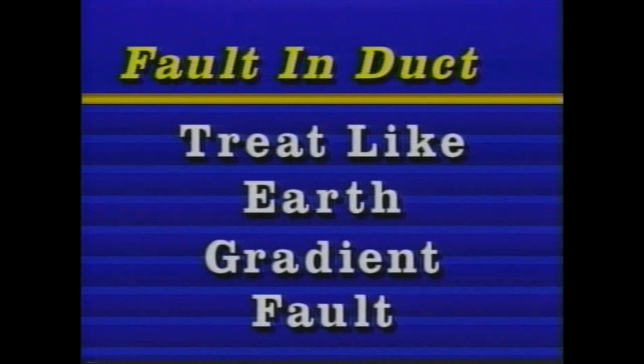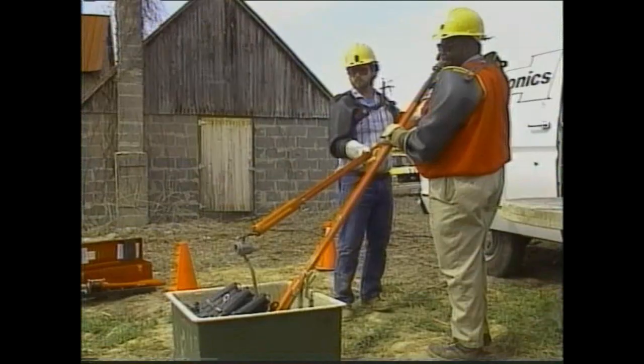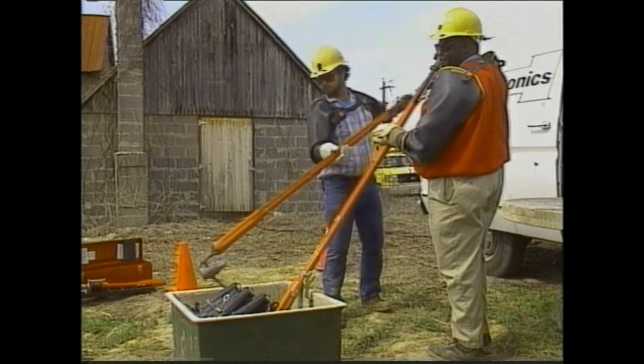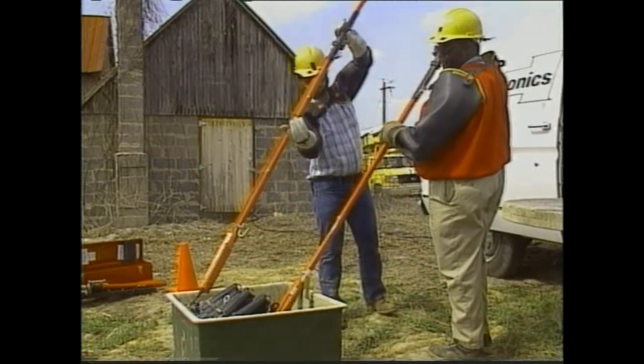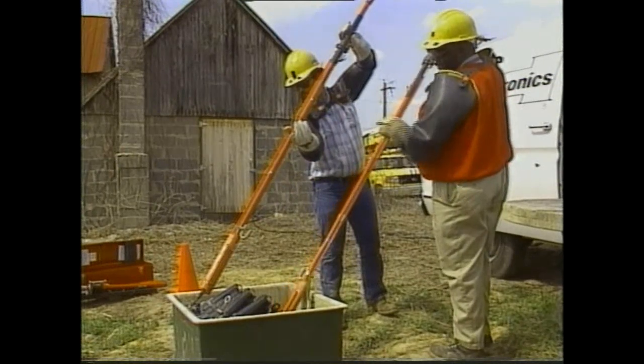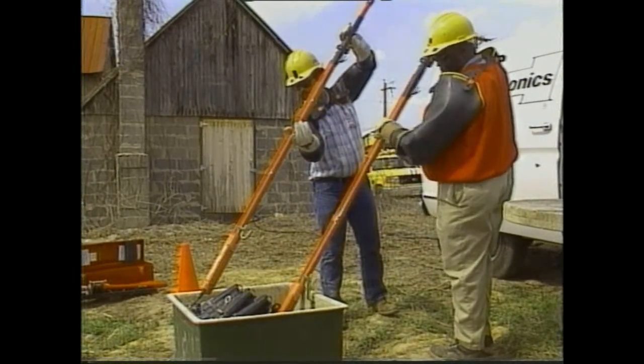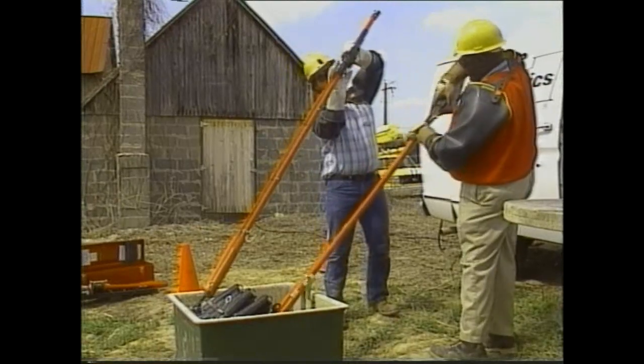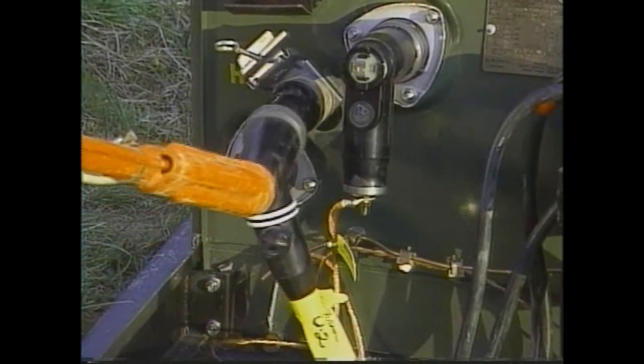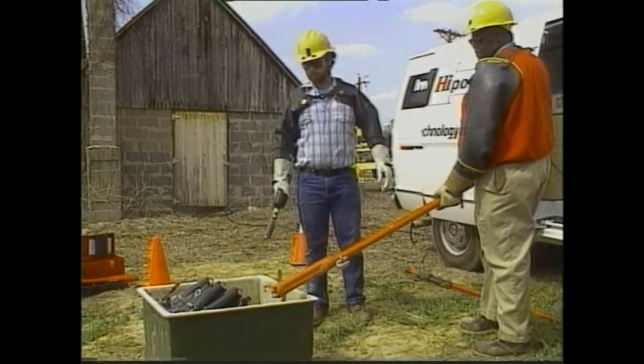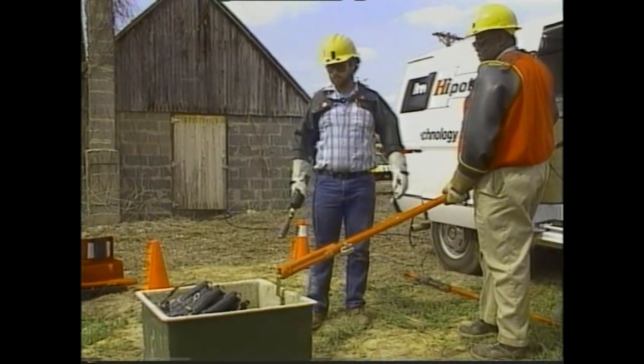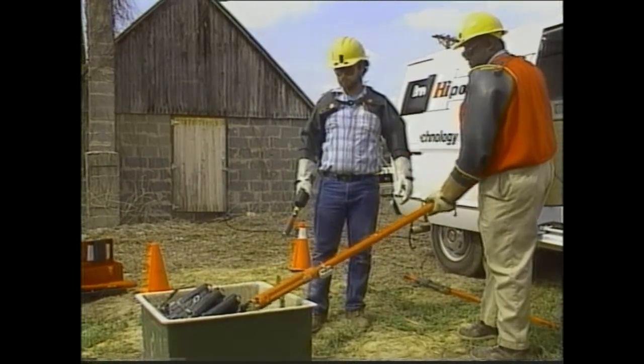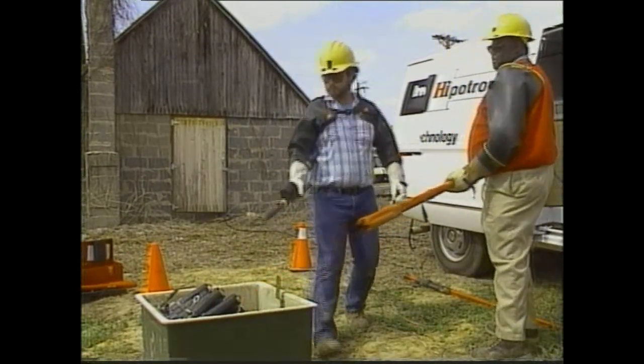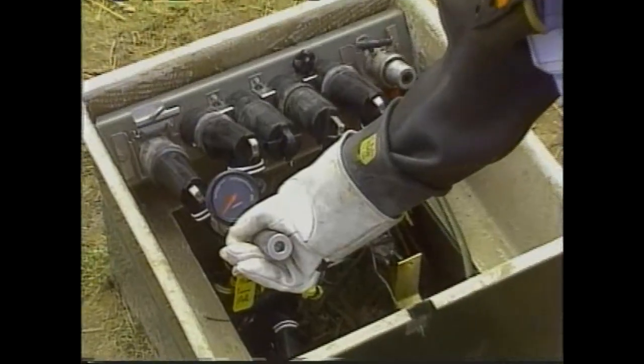Now let's go outside and locate a primary cable fault. This is the primary enclosure where we will set up for a primary cable fault locate. After we seal off the work area, make sure you have all of the live line tools that you need, including high voltage rubber gloves. First, we isolate the cables we are testing at both ends. In this enclosure, we begin by finding the cable that is not energized and possibly faulted. Using a shotgun stick, we remove the test cap cover on each elbow. We test for current with a high voltage voltmeter.